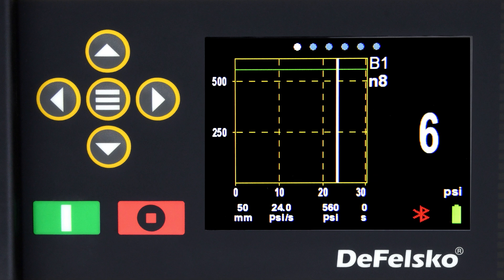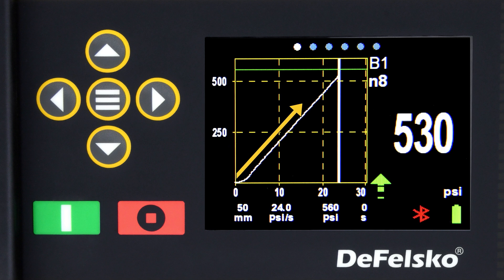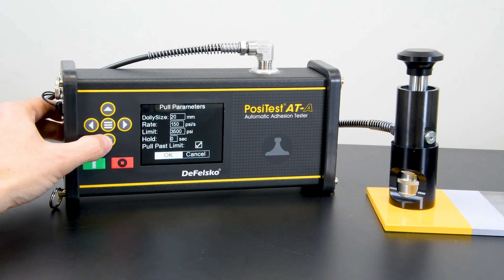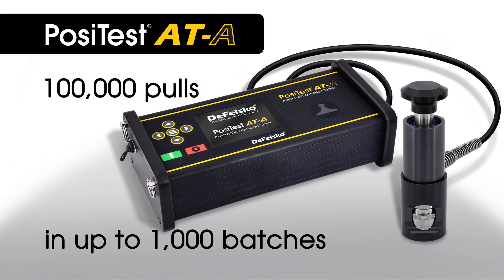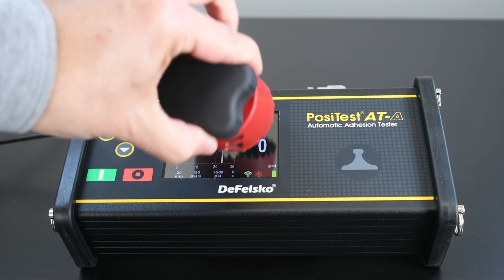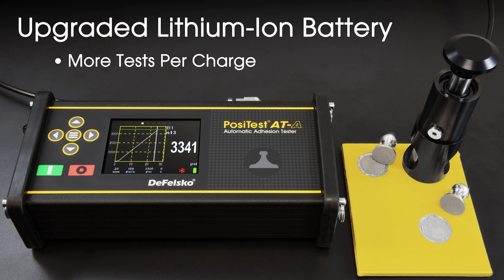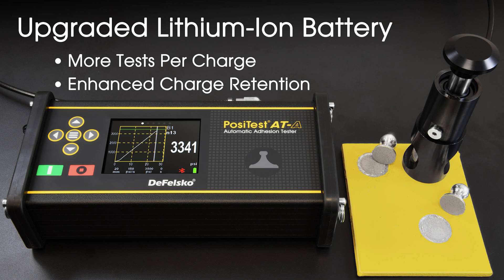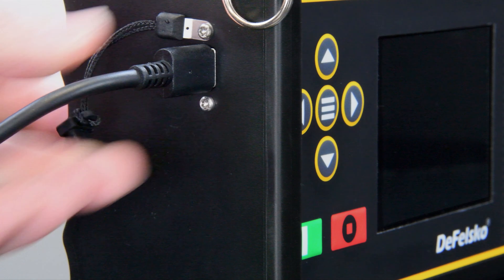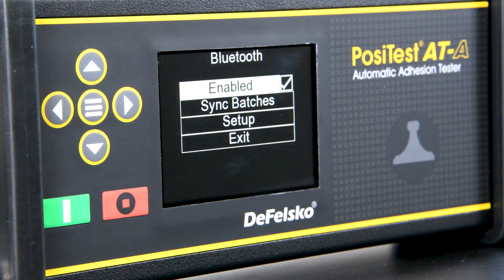The PosiTest AT-A automatic adhesion tester features an electronically controlled hydraulic pump that automatically applies smooth and continuous pull-off pressure with a user-adjustable pull rate, pull limit, and hold time. It can store test data for 100,000 pulls in up to 1,000 batches. The impact and scratch-resistant color touch screen and keypad is ideal for operation both with and without gloves. Upgraded lithium-ion batteries provide more tests per charge with enhanced charge retention during long-term storage. The USB-C port enables fast battery charging and can be used to operate the instrument while charging. Using built-in Bluetooth technology, measurements can be transmitted to the PosiTector app for further annotation.